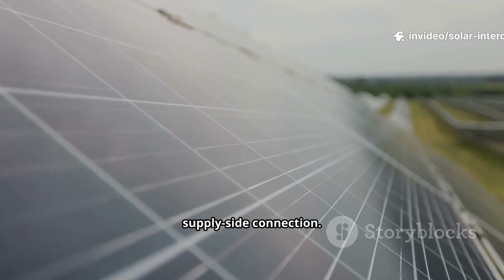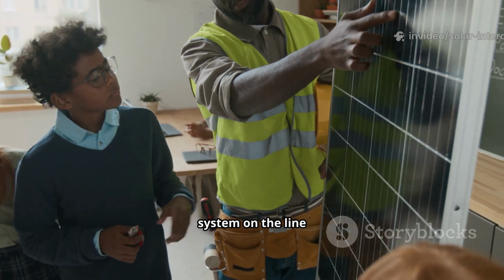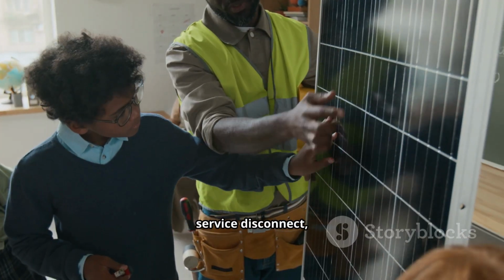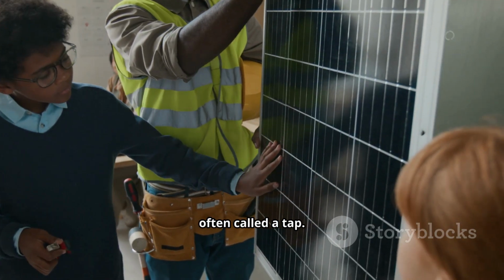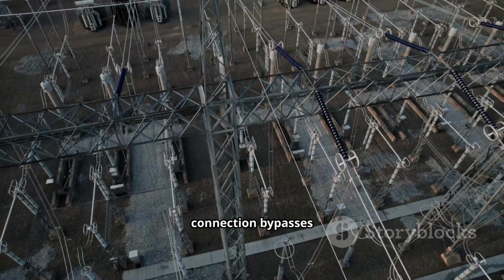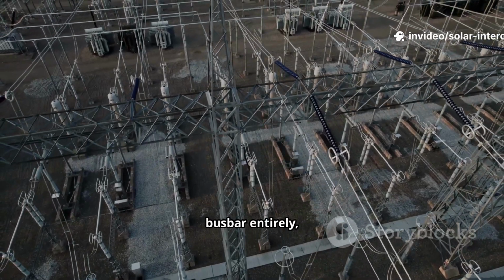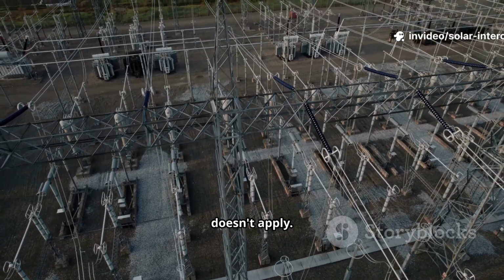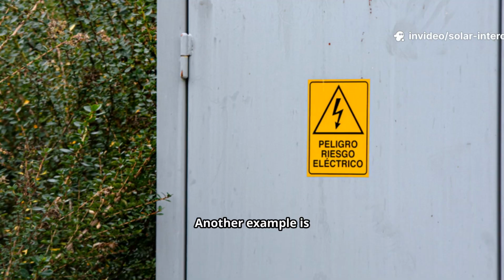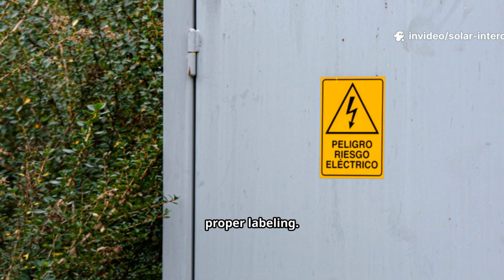One solution is to perform a supply-side connection. This means connecting the solar system on the line side of the main service disconnect, often called a tap. This type of connection bypasses the main panel's bus bar entirely, so the 120% rule doesn't apply. This is a very common solution for larger solar systems on homes with standard electrical panels, and is explicitly allowed by NEC 705.12(A).